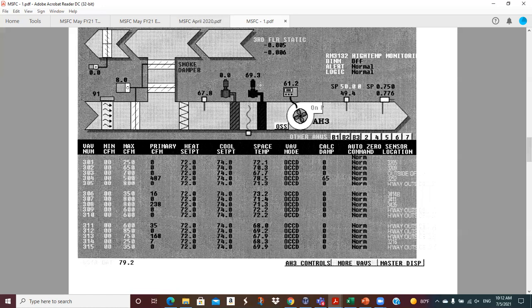69.3. That could be a percent, that could be a temperature. It looks like that's probably a percent on the valve right here. Here's our fan. This, I guess, is maybe a VFD setting. That may be 61.2% of maximum, but we're going to have to get some help to make sure we interpret these things right.